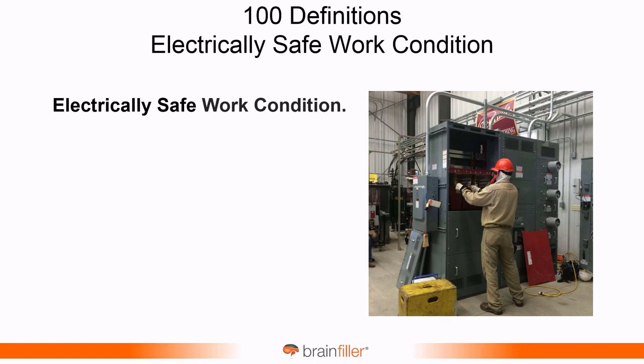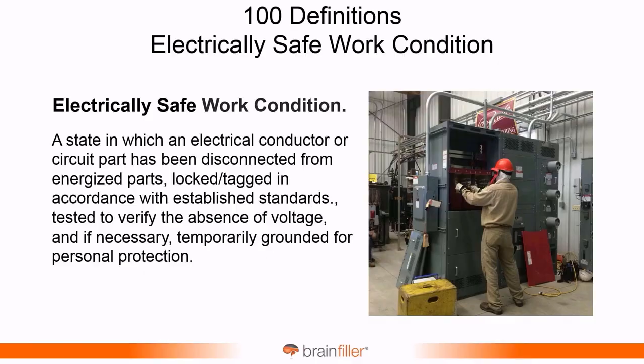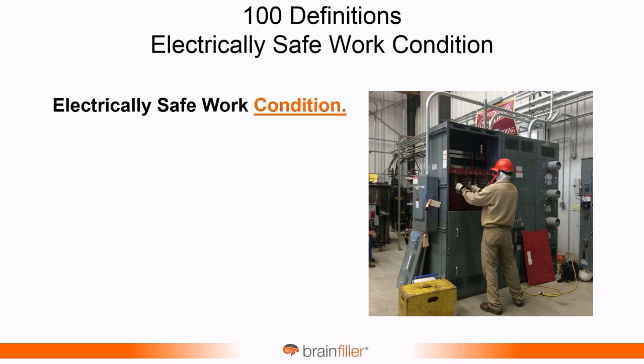The electrically safe work condition. This is quite an important change. I talked about the theme, as I referred to it, and how the electrically safe work condition is this reoccurring theme, and it keeps getting elevated to a higher and higher level. And there was a kind of a significant clarification. I don't want to say it's a major change, but it's a clarification to the term electrically safe work condition. So this is the definition as we've had it, and it's a state in which an electrical conductor or circuit parts has been disconnected from energized parts, and we know the rest of this. But what has been clarified is the word condition, electrically safe work condition.